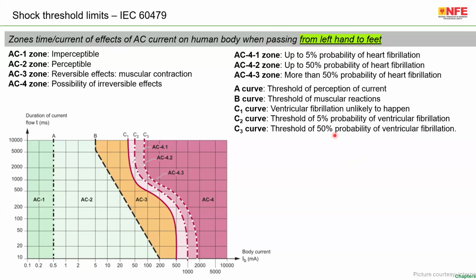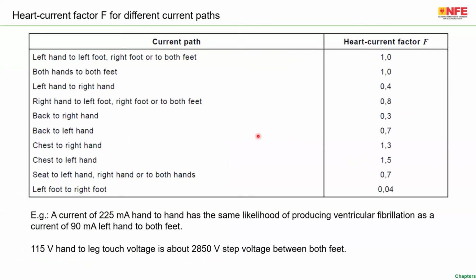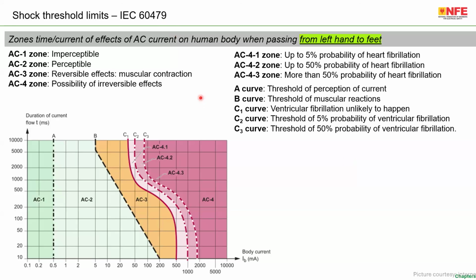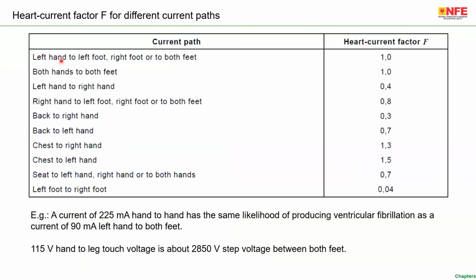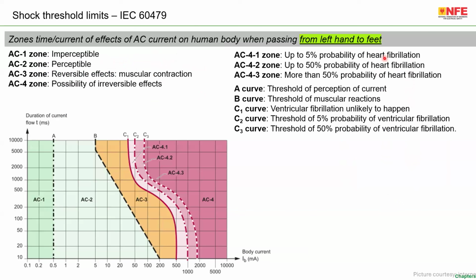Now we have to look at an interesting subject, which is called the heart current factor. You can find this information in the IEC standard, which I have just shown you, especially IEC 60479. The heart current factor is a factor set by the standard to decide various touch voltages and step voltages. For example, for left hand to left foot, or right foot, or both feet, the current factor is 1. So whatever the touch voltages in this particular graph, we are supposed to meet AC1, AC2. Don't go to AC3 and the higher ones.